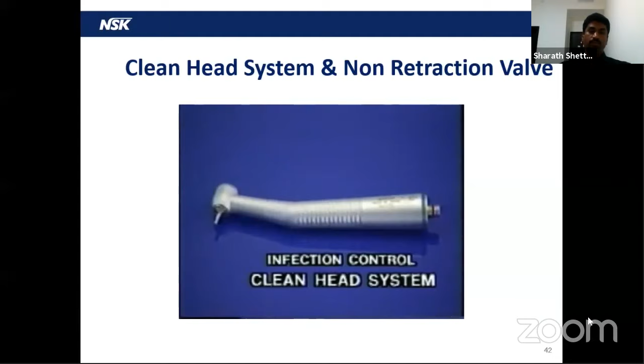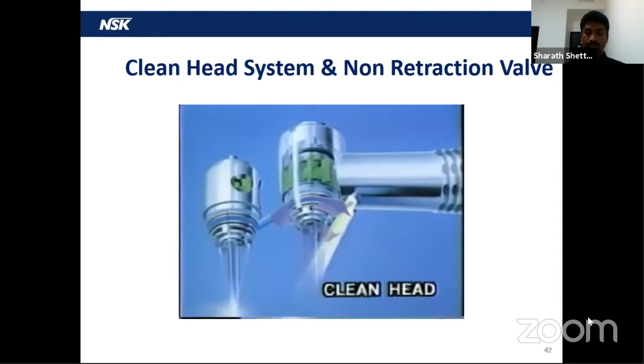These problems were thought to have been inherent in the dental handpieces. Nakanishi Dental tackled these problems and found a solution, both in the airline and the water line. The non-retraction valve prevents water drawback. And the clean head mechanism prevents back suction of foreign matters into the head.